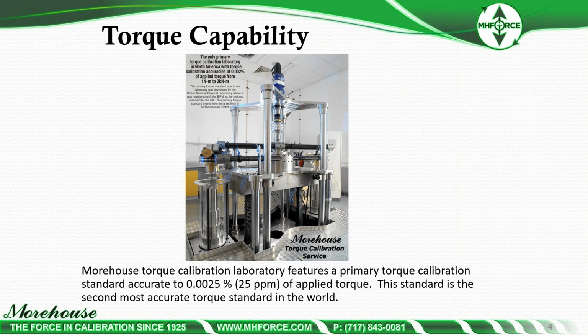On the torque side of things, we bought the standard from NPL United Kingdom. We do calibrations in accordance with ASTM E74 and other standards, such as BS 7882, which we may be dropping because there's just not a lot of BS 7882 work coming to this country. That's kind of similar to how ISO 376 works, with the exception that every year we're doing more and more ISO 376 calibrations. There are requirements, and people are asking for it. But BS 7882, we've had that on our scope for years, and we get like one request every 3 or 4 years. So it may not be a standard that we keep up for torque.